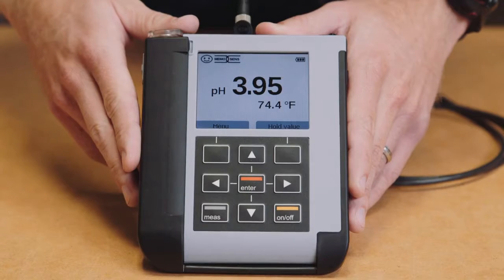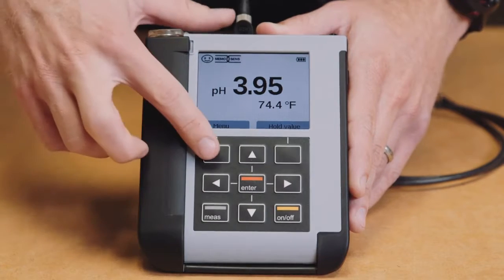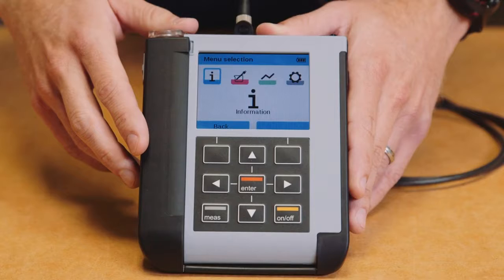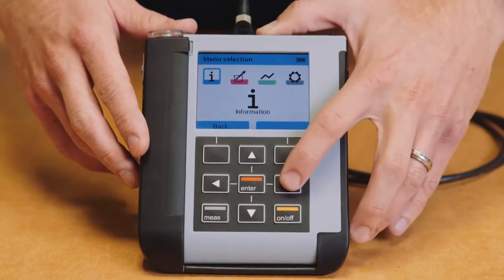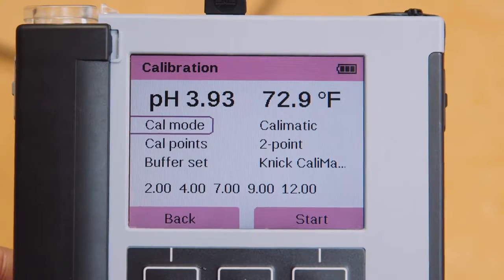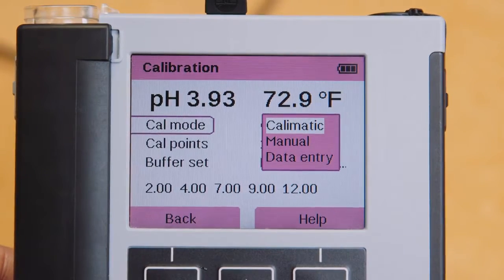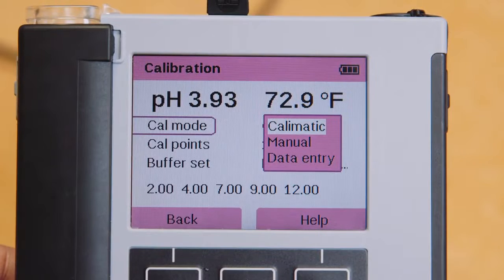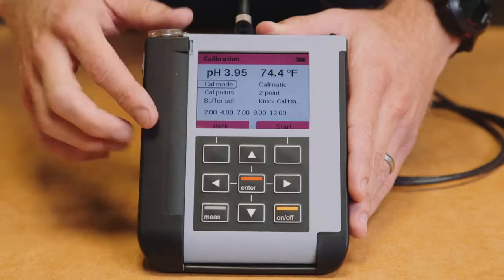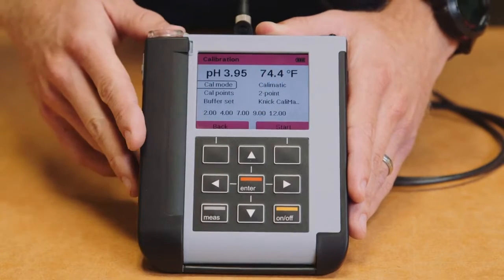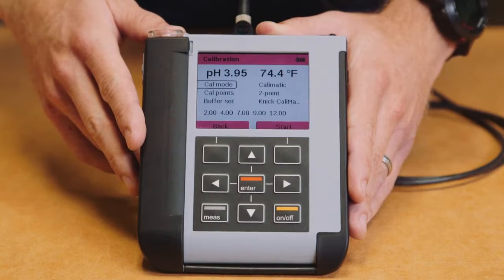To start the calibration process, press the upper left button to go into the main menu screen on the Portavo. Then, navigate to the calibration menu and select Enter. There are 3 options for the cal mode. We recommend Calimatic or automatic calibration with at least 2 points of calibration. In Calimatic mode, buffer solutions are automatically recognized and compensated based on the temperature reading from the integrated temperature detector.